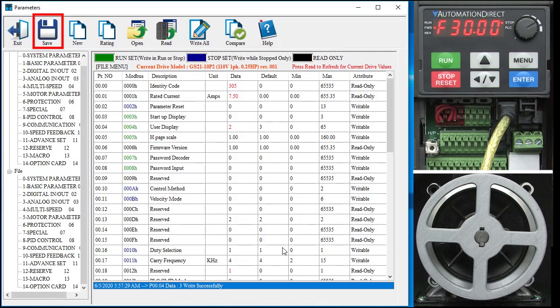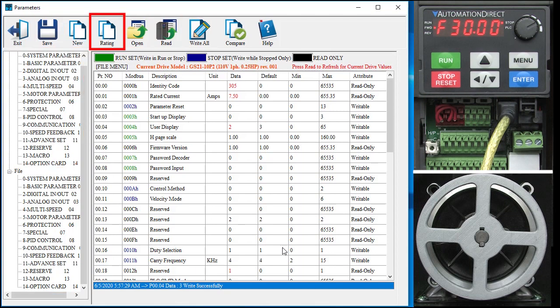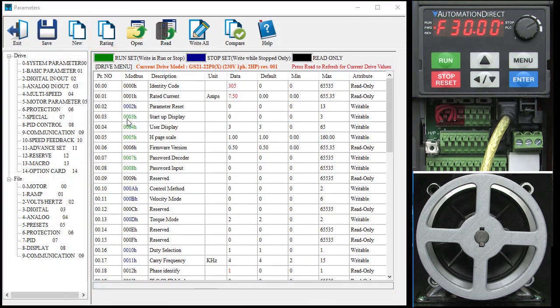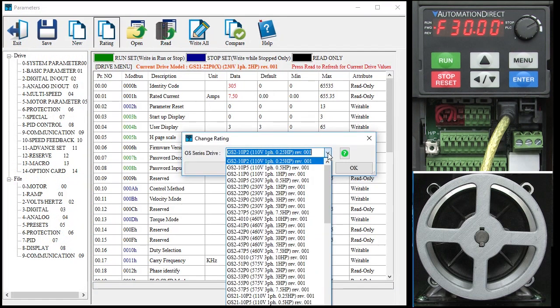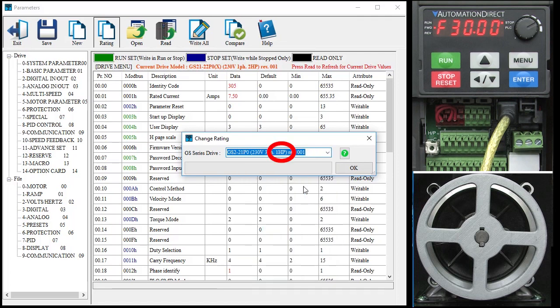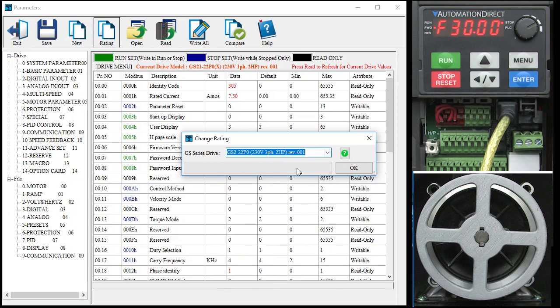So save, open and new are disk file operations. Read and write are drive operations. The rating button is to change the drive rating type in the file parameter set. For example, if I have a 1 horsepower GS20 configured exactly the way I want it, I can download that configuration file into a 2 horsepower GS20 by simply clicking this button and changing the drive rating in the file.